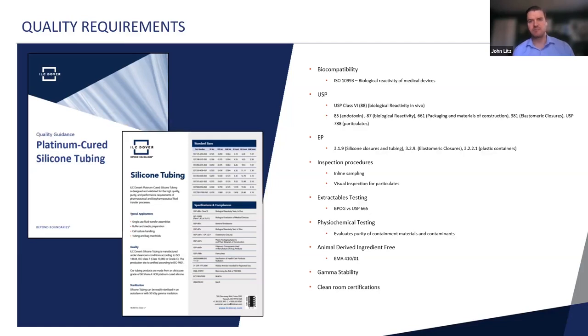Some of the main things you're going to see is biocompatibility testing. That's generally done to the ISO 10993 method for biological reactivity in medical devices. The ISO 10993 is actually a series of multiple tests—I believe 20 or more tests that make up that standard, not all of which apply for tubing, but it is a very rigorous series of tests that this tubing needs to undergo to ensure that it's going to be safe for use in the drug manufacturing process.